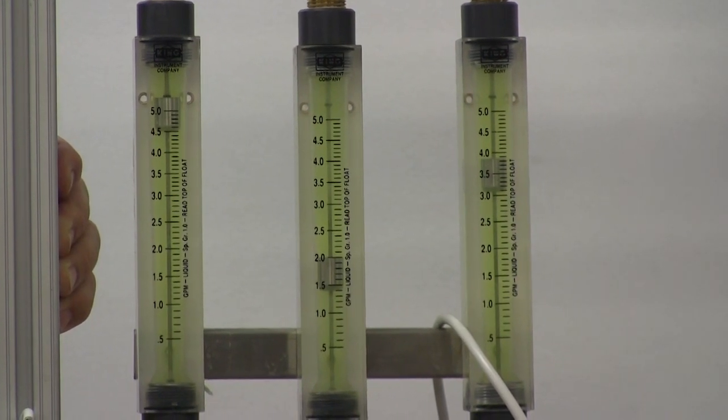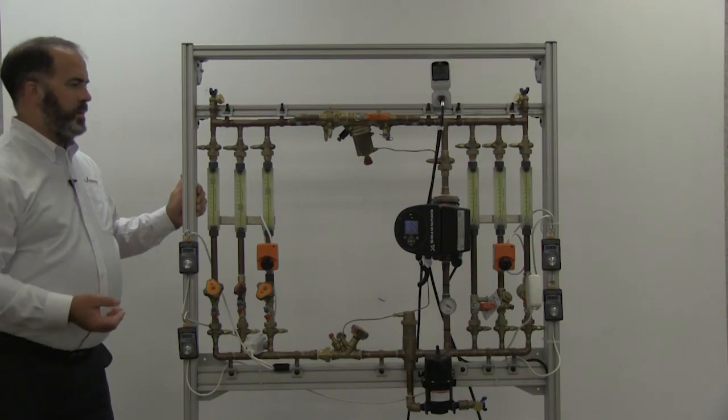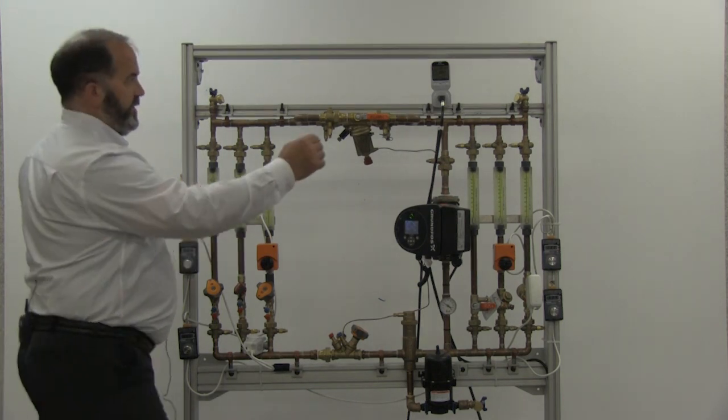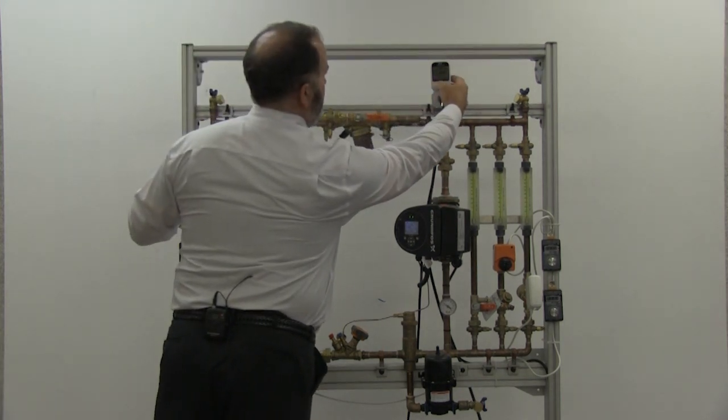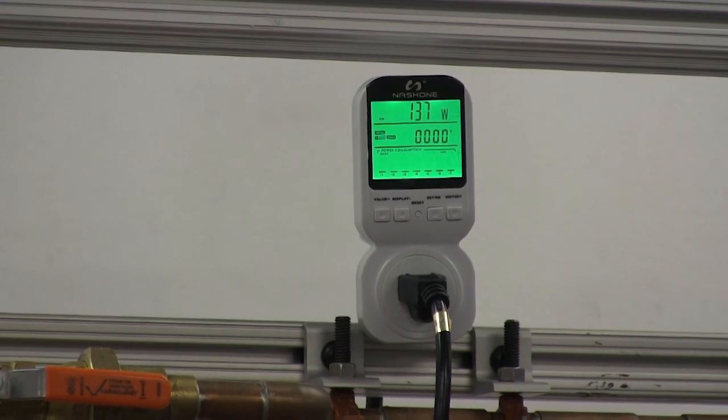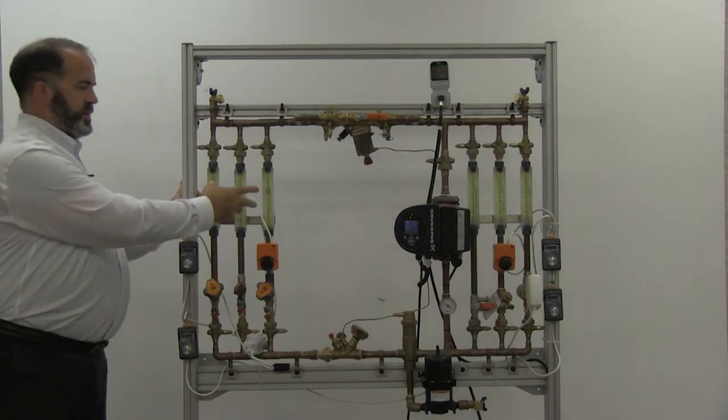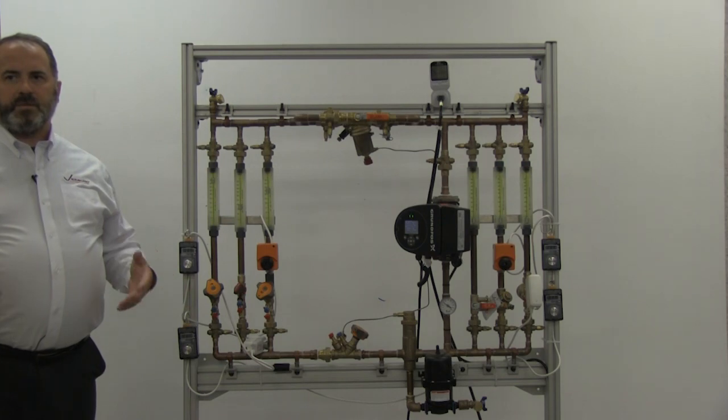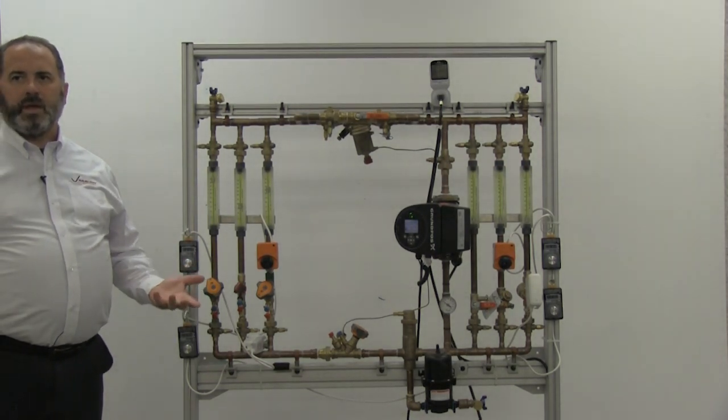But just by doing pump optimization with an unbalanced system, the benefit of doing that in terms of energy, I'm at 137 watts now. But you'll notice I'm still overflowing the system. I'm still moving more liquid than I have to.